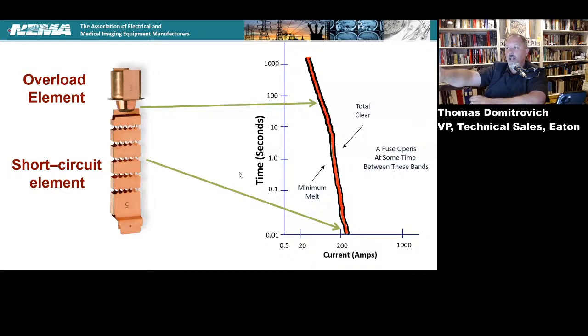And that's why that portion of the element is what gets you your current limitation and for the high fault currents. Now, for the low fault currents, we have the overload element, and the way that's designed is, and everybody does it a little bit differently, but the principle is the same. There's like a dab of, I don't know, something that's meltable at a lower temperature. It could be maybe a little bit of lead or other materials in there, and what'll happen is the plunger that's connecting that base unit with the number 3 on it to the portion of it that has all those pinch points, that's being connected under the force of a spring that wants to pull it apart. So what happens is when that melts, that spring acts to pull that apart, but it melts at lower amperage values, but because it's melting, you're looking for a longer duration of current. So you need current and you need a lot of time to heat that up to get it to a melting point where it will disconnect.